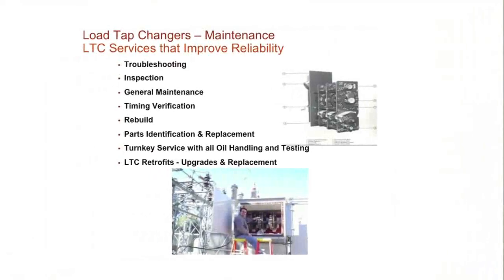Uprating potential. We talked about the knowledge, but at that time you can look at uprating the transformer in some cases. The limiting factor may be the LTC, is what we found. In some situations where we put a larger LTC on, you can get more capacity out of the unit itself, because the current carrying limitations of the previous LTC were lower than what the rest of the unit may be able to handle. So you can also look at uprating at that time. Many of the tap changers, I'll say, were and are good designs.